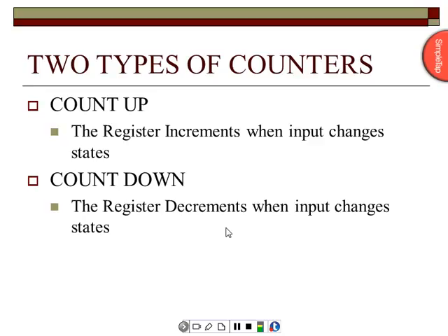Actually, I'm going to have to check that and make sure, but count down counts 0. So on the count up, you're sitting at 0, your next one is 1. With the count down, it actually counts the 0, so if I need to count down to 7, I'm going to put it in as 6 because it counts the 0. So it's 0, 1, 2, 3, 4, 5, 6.